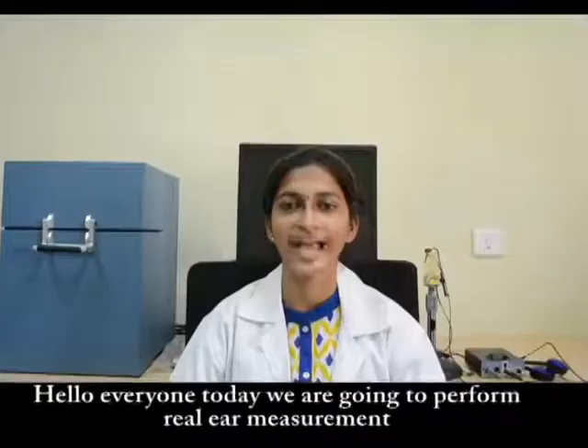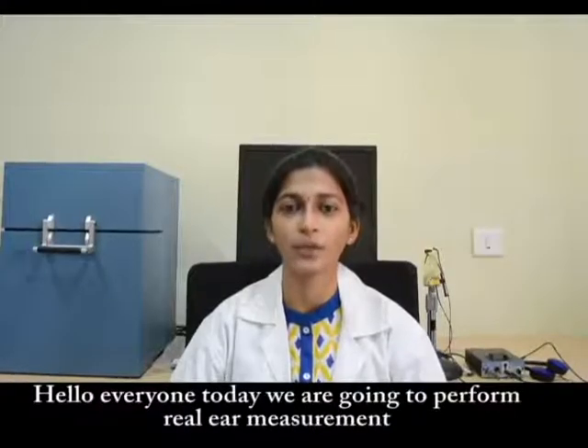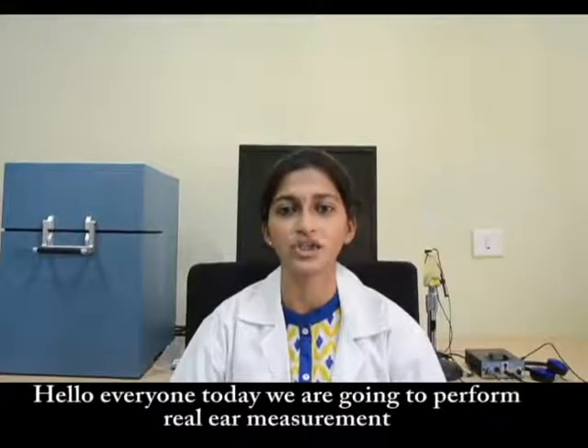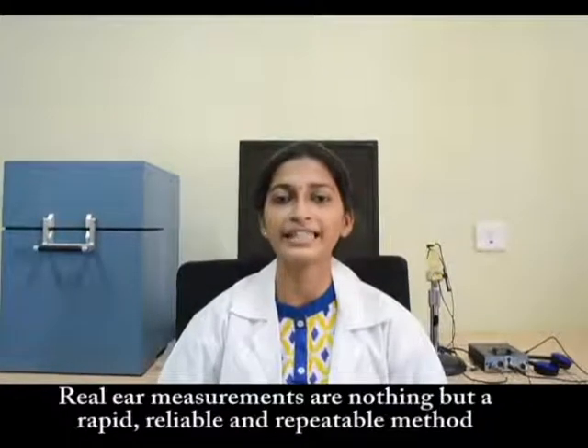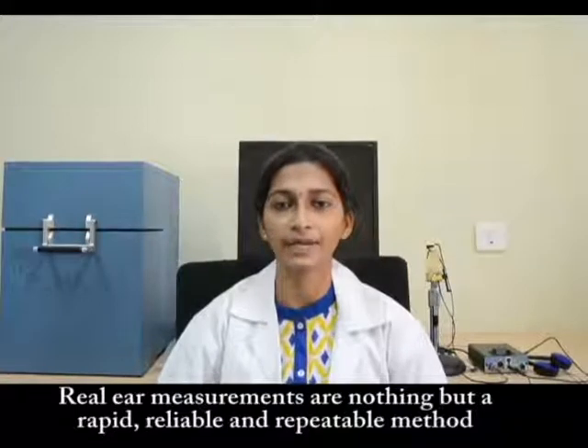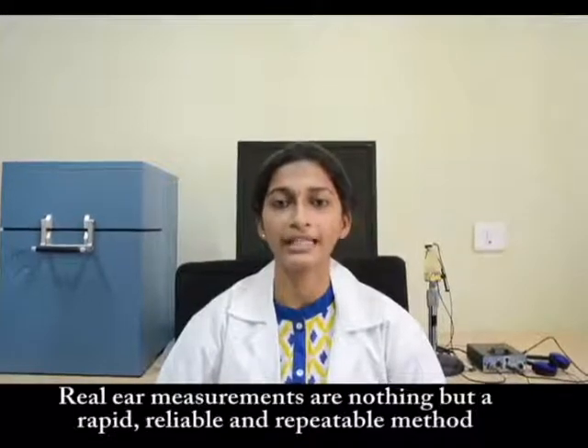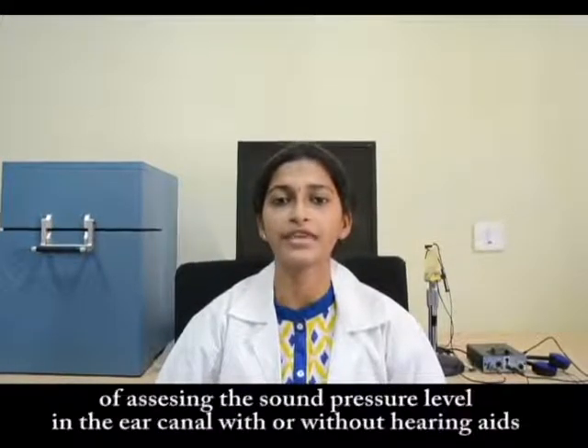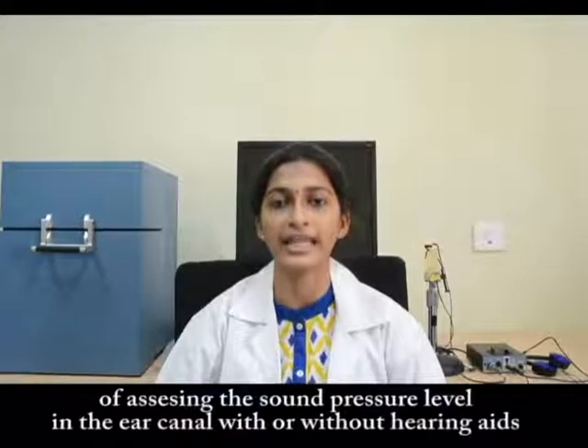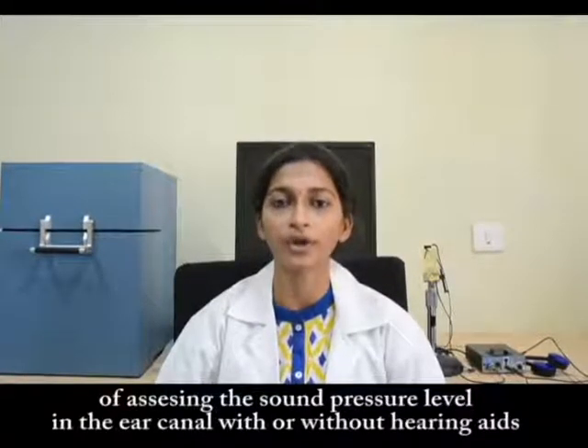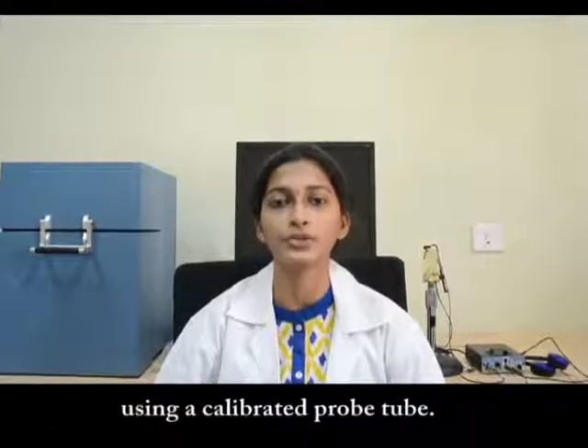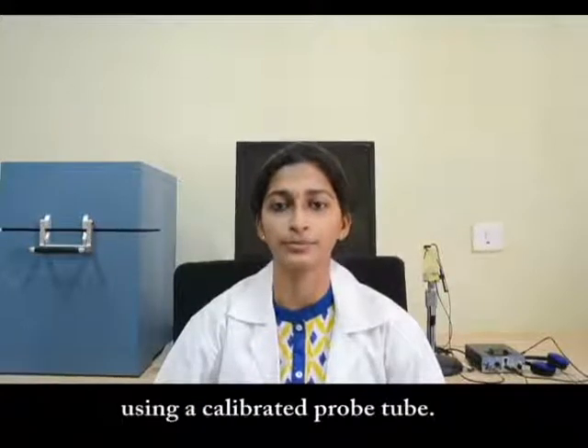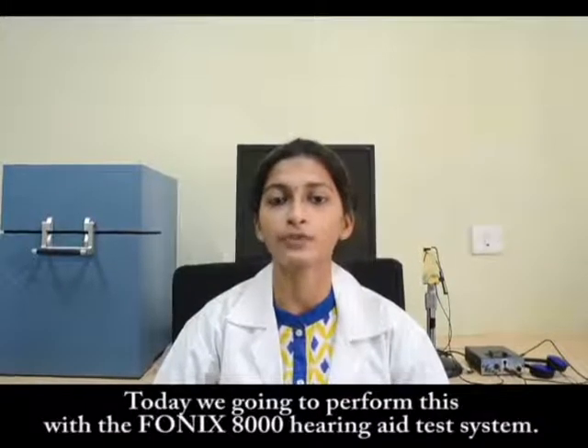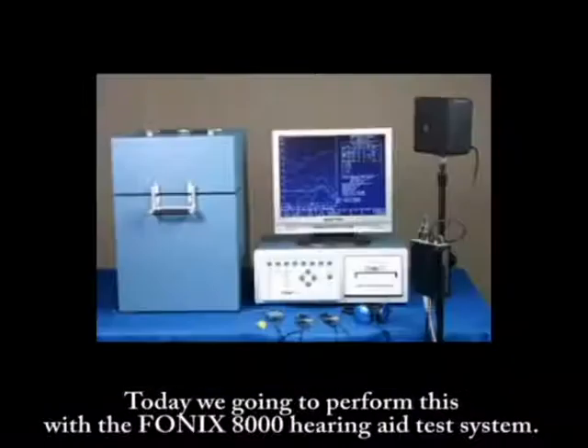Hello everyone. Today we are going to perform real ear measurements. Real ear measurements are nothing but a rapid, reliable and repeatable method of assessing the sound pressure level in the ear canal with or without hearing aids using a calibrated probe tube. Today we are going to perform this with the Fonix 8000 hearing aid test system.